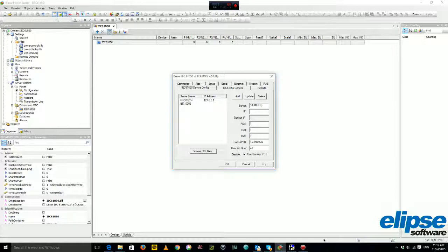Okay, so this one is the Siemens IED, so I can write a proper name here, and I can set one IP because the IP is missing from the ICD file, so I just write a correct IP. Also here I have a value, and the ICD file has this option checked by default, so I have to uncheck this. Every time you make a modification, you must click on update. If you don't and just press OK, when you come back there are no changes. So you have to make sure you click on the update button.